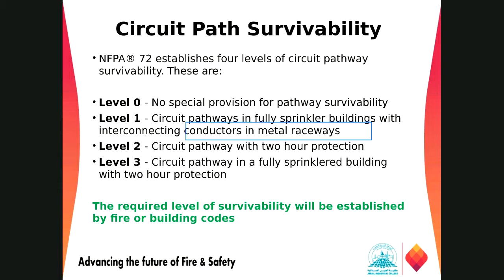Level 2 is for 2-hour protection. So if there is a fire for 2 hours, your circuit is not going to be damaged. And level 3 is the fully sprinkled building with 2-hour fire protection.